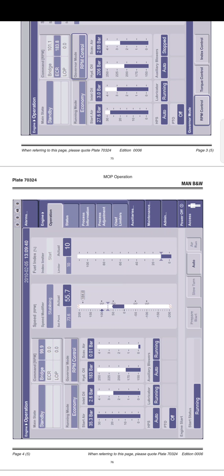Available limiters are start. The start limiter defines a fixed amount of fuel to be used for the first injections during start. Chief. The chief limiter defines a maximum amount of fuel to be injected according to the settings done by the operator at the screen cylinder load. Scavenge air pressure. The scavenge air pressure limiter defines a maximum amount of fuel to be injected based on the actual scavenge air pressure in order not to overfill the engine.